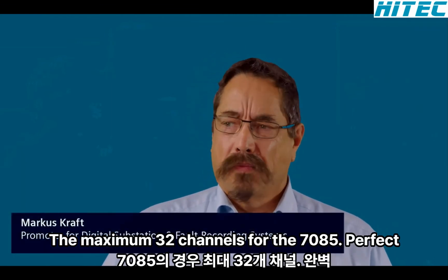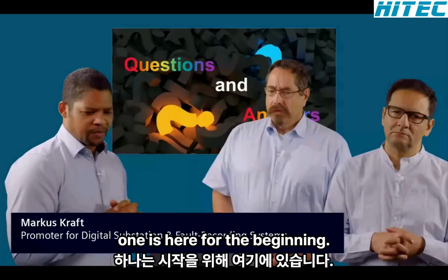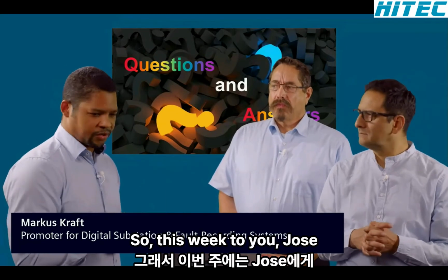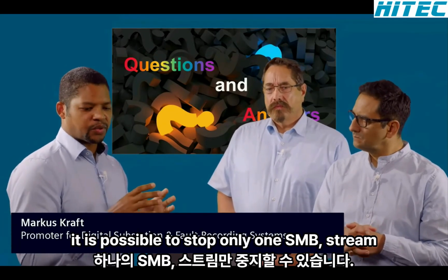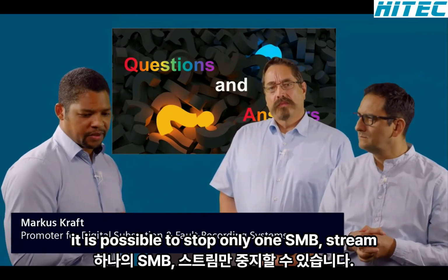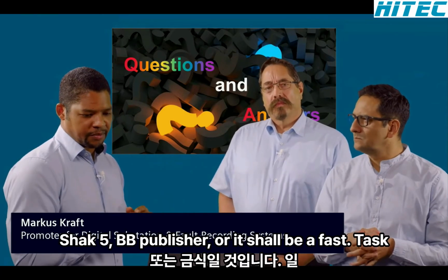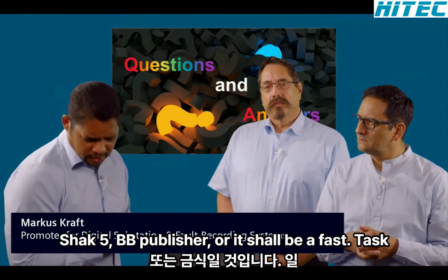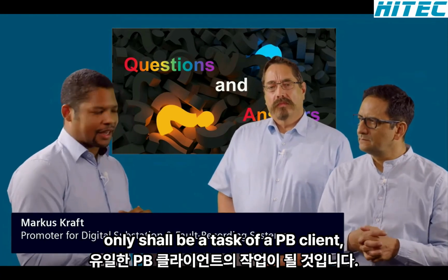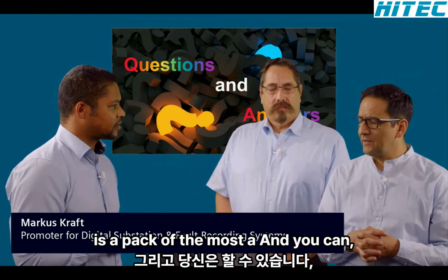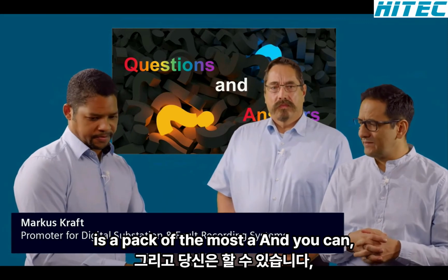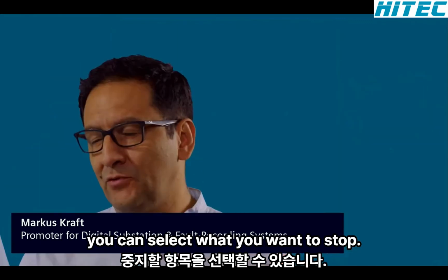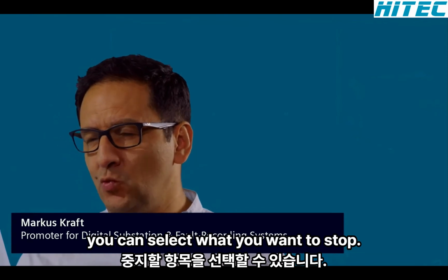Okay, perfect, Marcus. Another one is regarding the beginning, so this goes most probably to you, Jose. Is it possible to stop only one SMV stream in the SIPROTEC 5 PB publisher, or should it be a task of a PB client? It's a task of the process bus server, the merging unit, and you can select what you want to stop.